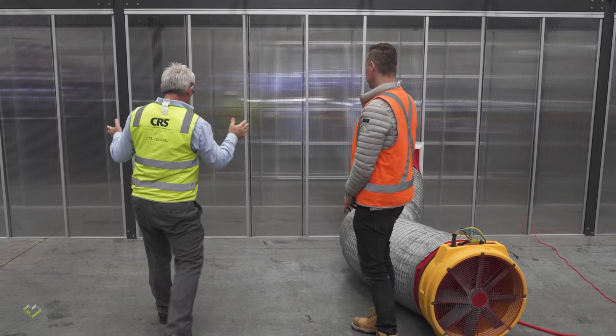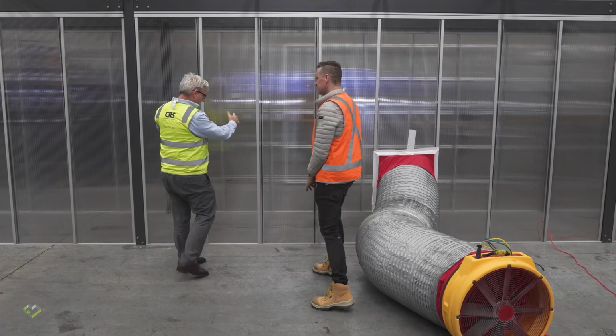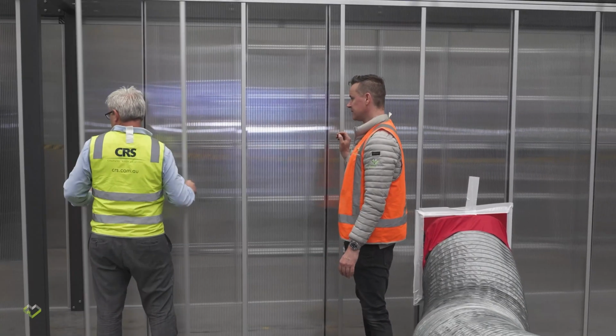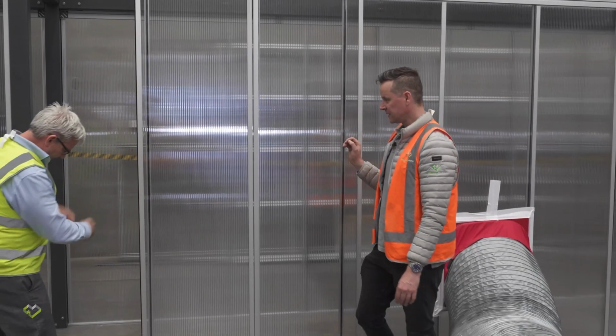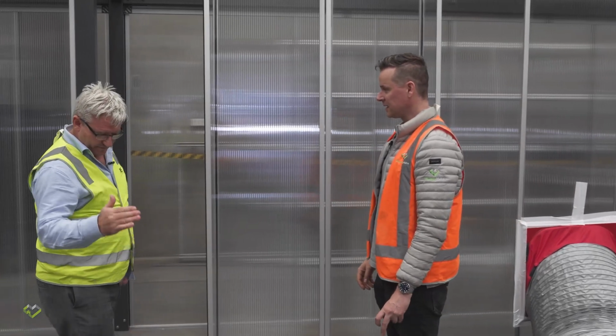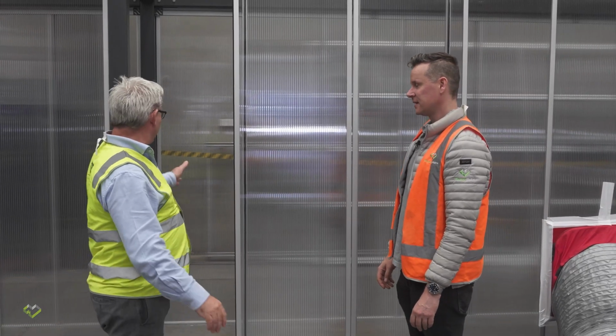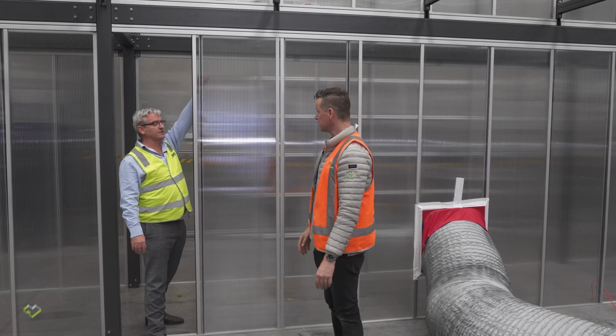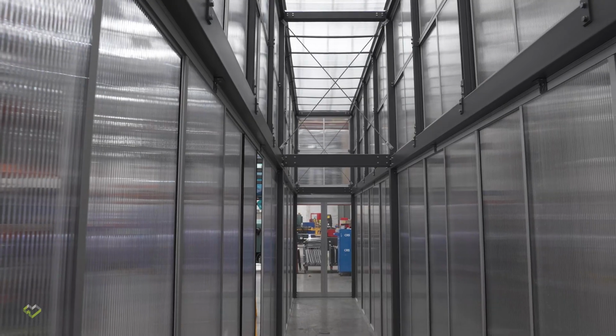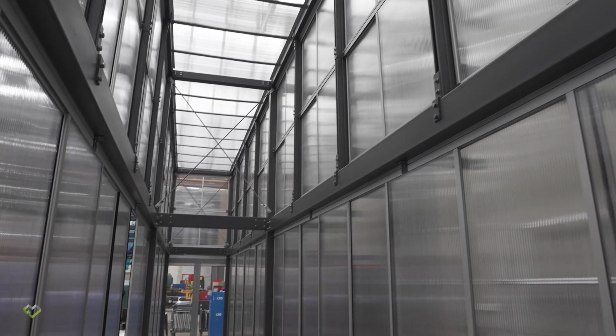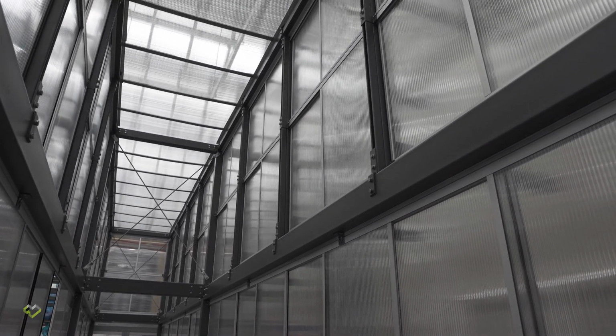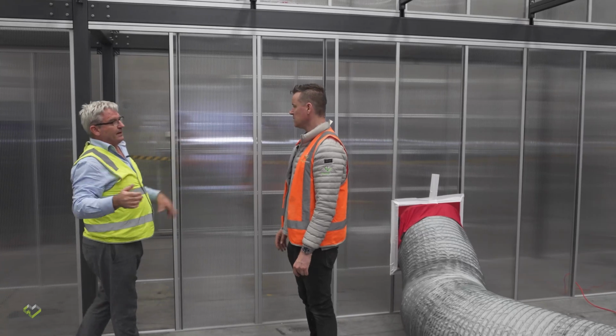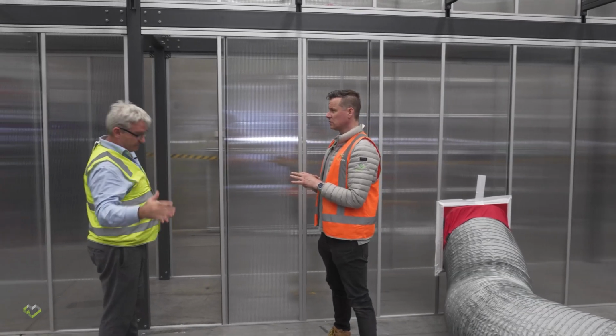So this structure here would be simply bringing a server rack in here, removing a panel, lifting up the floor track, sliding a server rack in. Front door here, bringing the cold air in, hot air here, extracting the hot air out. So keeping that hot air that you're expelling from the back of the racks from mixing with what you're injecting at the front. And getting it back to the hot air plenum, ceiling plenum. And then running it back to your fan walls or your CRAC units with your pressurised corridor or your fan wall back to the perimeters of the data hall. And then obviously sending that cold air back through again, back through the racks.